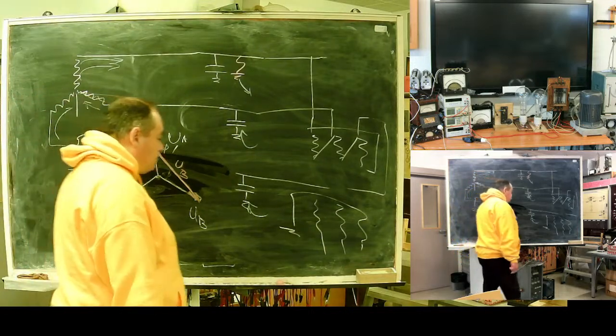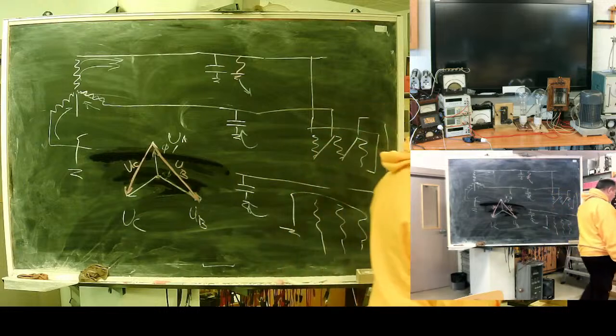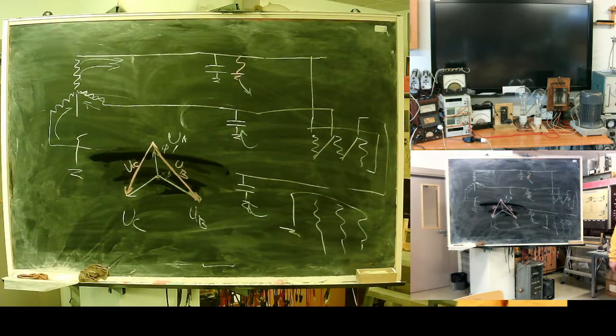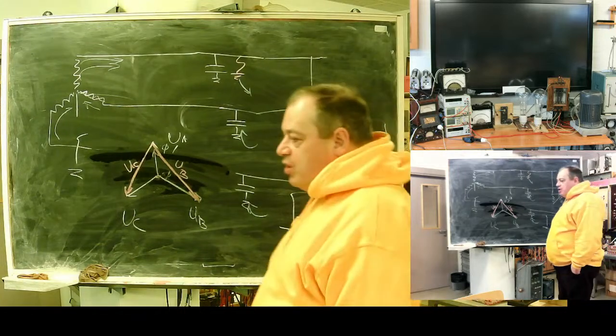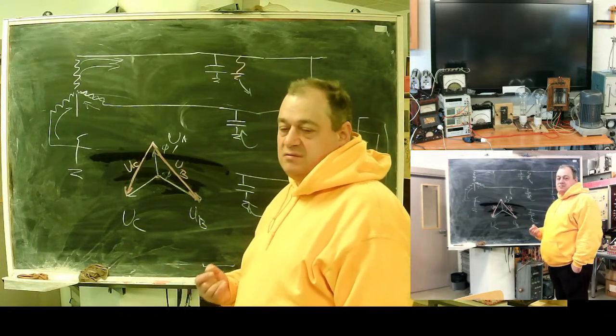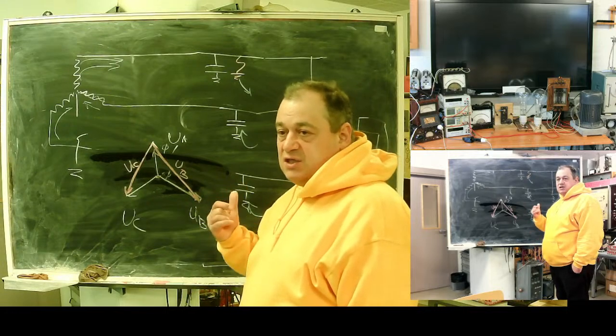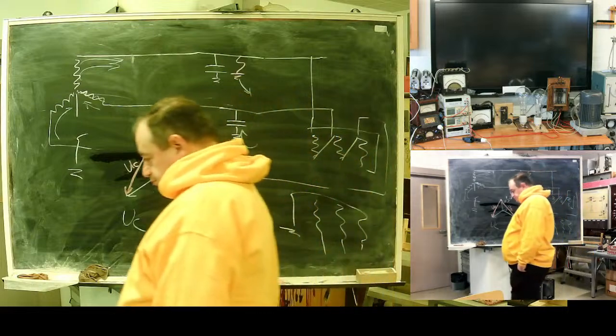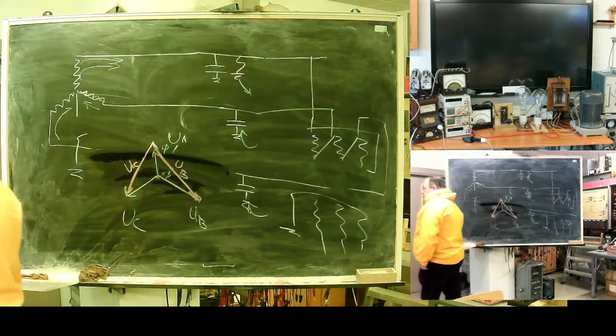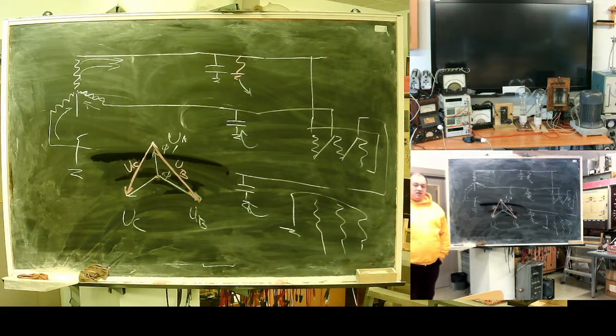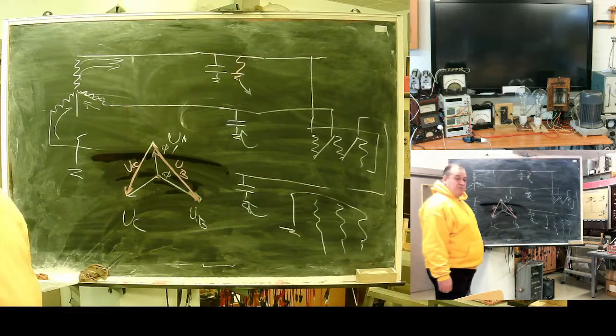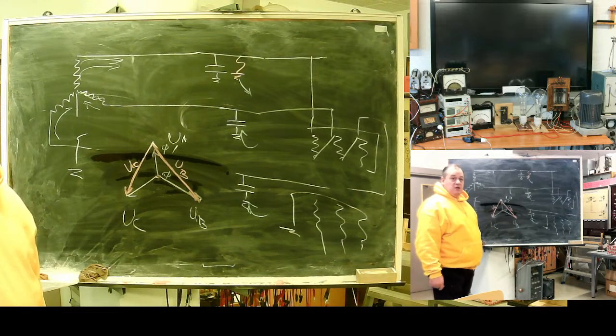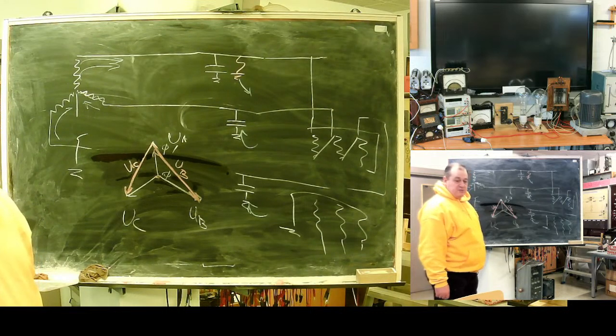So such networks offer us good statistics. We have a fault, and an earth fault is the most probable, and we can continue operation. So why is earth fault protection needed, you can ask. In general, in all time, it wasn't needed. Only a signal from the three-pole to zero, that we have a fault. And we had 8 hours or more to find this fault and do something.